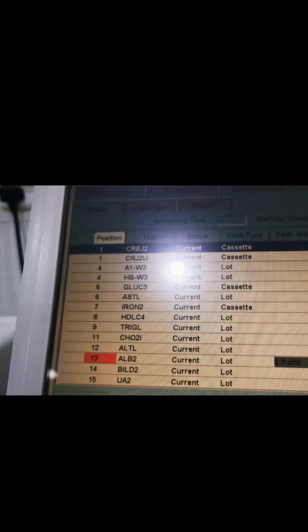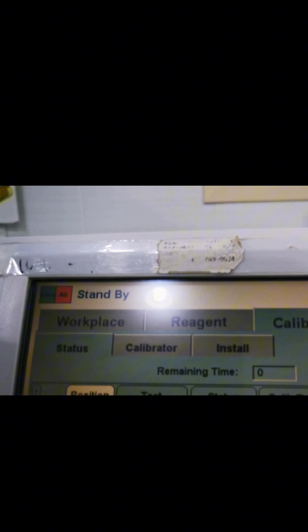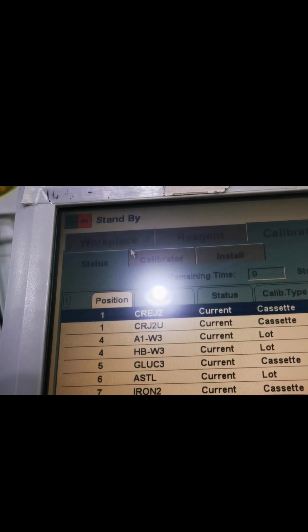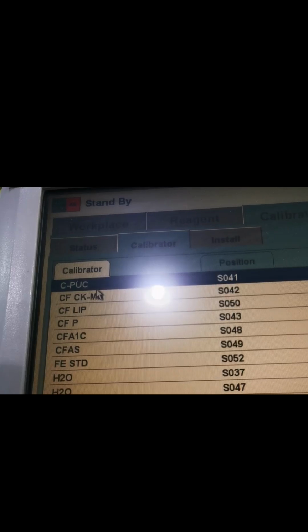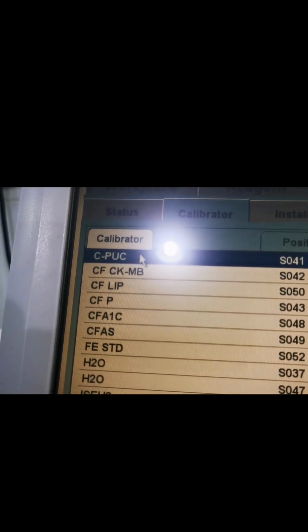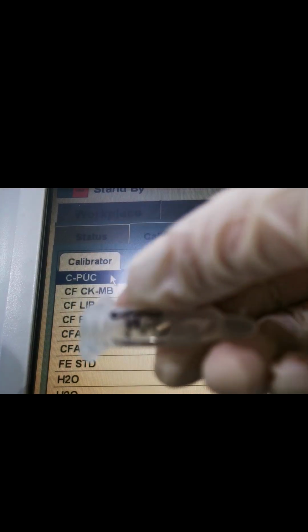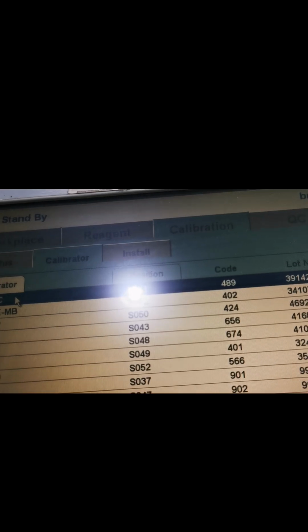How to calibrate? First we will click the calibration, then let's go now to the calibrator. Just click calibrator. Why do we need to click the calibrator? We need to click the calibrator to see the position of the calibrators that are installed here in our machine. For example, for the microalbumin, we have the CPUC, position number 41. So, for our calibrator for the microalbumin in urine, we will place our calibrator in the number 41 position here in our disc.